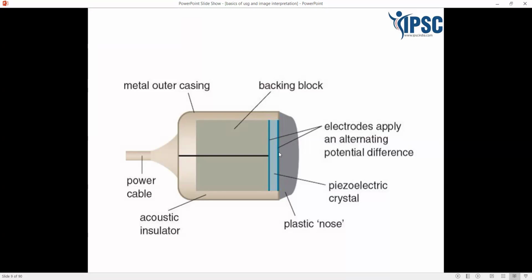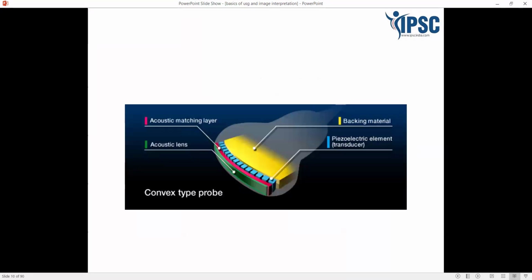Now, these ultrasound beams are emitted in all directions, but on three sides it is covered by a metal casing, which does not allow the ultrasound beams to pass, except on one side, which is the plastic nose through which the piezoelectric crystals allow the ultrasound beams to pass. So, though the beams are produced everywhere, they pass out only through this plastic nose. Okay. Now this is the cut section of the probe, showing how the crystals are placed. As you can see here, we've got the acoustic lens, the acoustic matching layer, and this is all the backing material, and this blue one is the piezoelectric crystals. So these piezoelectric crystals actually emit the ultrasound beam and also receive it back.